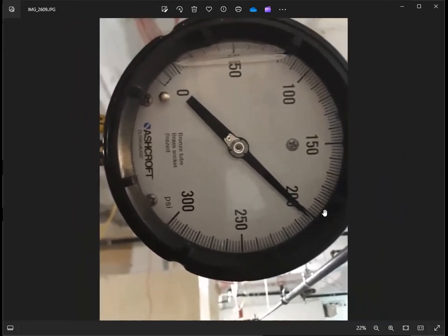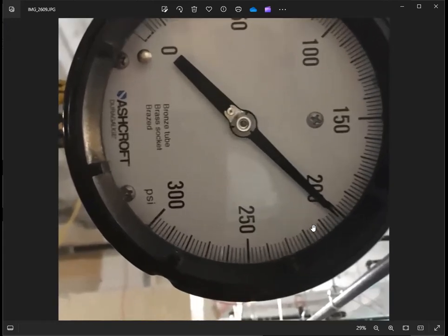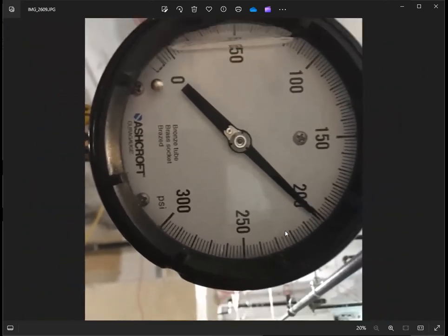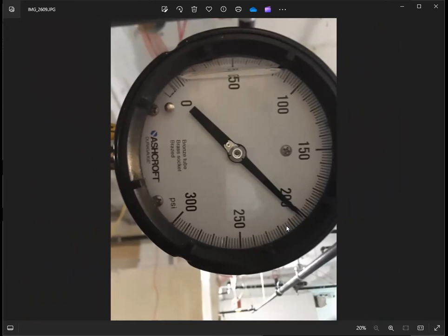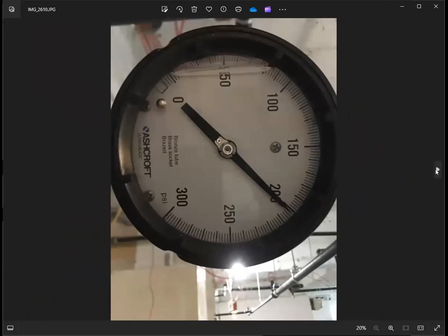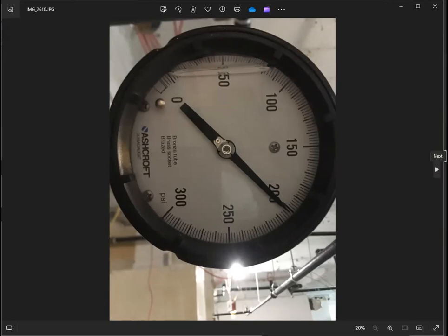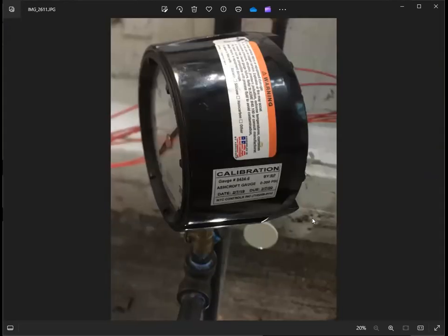So if in any case it got dropped for a certain amount of time, you need to at least restart your test, restart your time for 2 hours just to be sure that the system, the pipe connections, joints are totally leak free. There are some areas that you cannot see or that are not accessible for you to see. So one of the best indications is the pressure, if it's holding the pressure within the system, within the piping system.